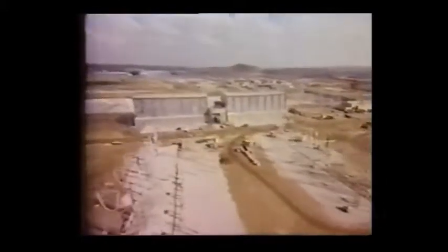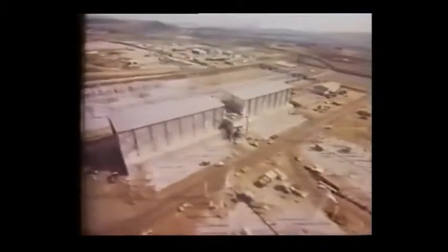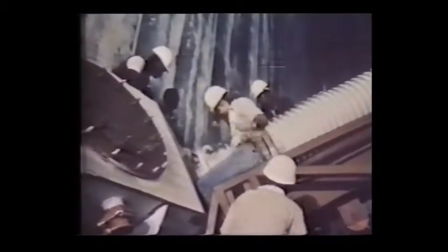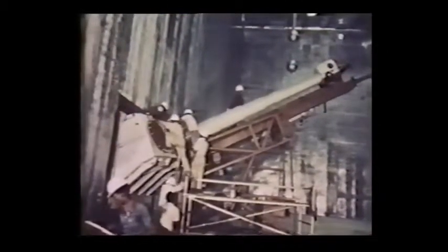Here at Kolwezi, another station will convert the direct current to alternating current. Both converter stations will be expanded as power needs increase. Within the cavernous Kolwezi valve halls, electrical equipment will change direct current into 220 kilovolt 3-phase alternating current for distribution in the Shaba region, with 110 kilovolt service available through step-down transformers.